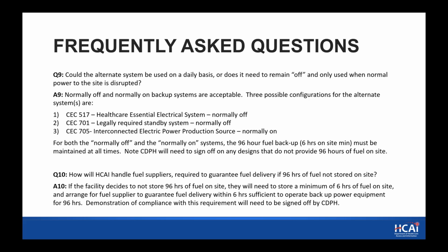Number 10. This keeps coming up: how will HCAI handle fuel suppliers required to guarantee fuel delivery if 96 hours is not stored on site? If the facility decides not to store 96 hours of fuel on site, then we'll need to store a minimum of 6 and arrange for a fuel supplier to guarantee. Again, demonstrations of compliance with this requirement will need to be signed off by CDPH.